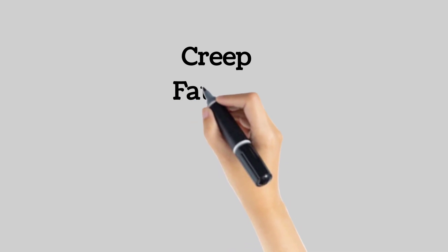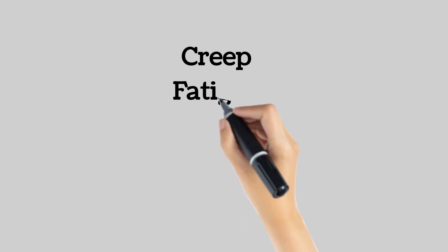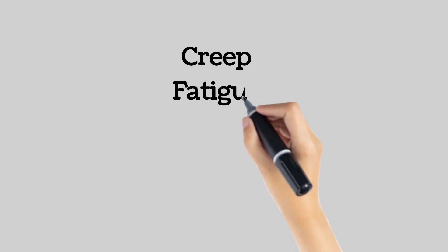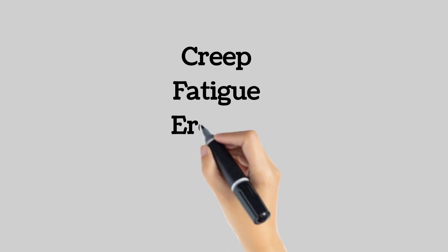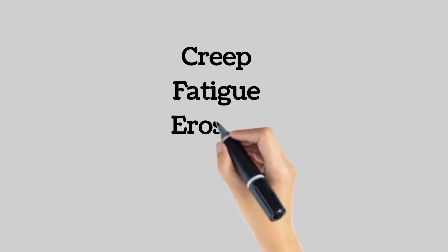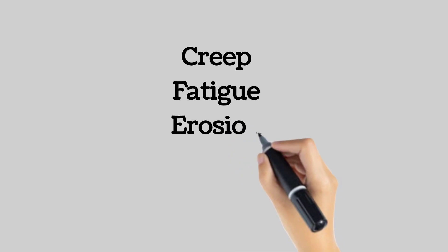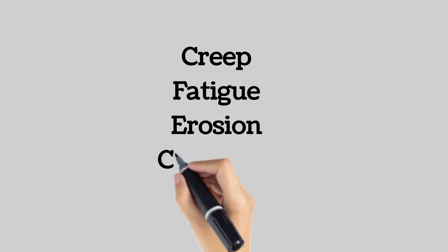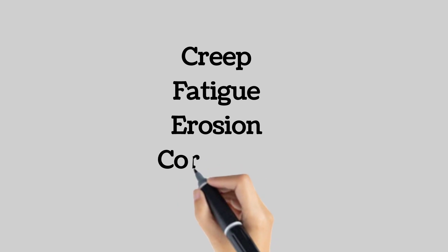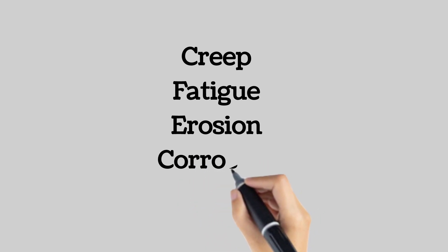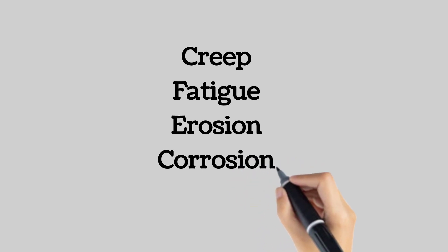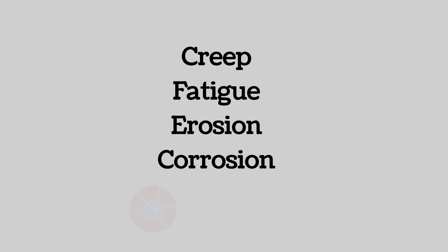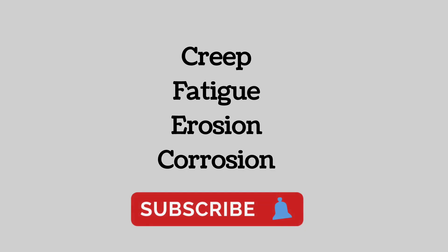Fatigue damage in materials is caused by cyclic loading with sufficiently high stress amplitude, resulting in initiation and propagation of cracks. Erosion damage is caused by the impact of particles on a surface resulting in loss of material, which means a reduction of material available to carry the load. Corrosion damage develops with certain combinations of material type and environment, and is caused by an electrolytic reaction which leads to erosion or crack formation.